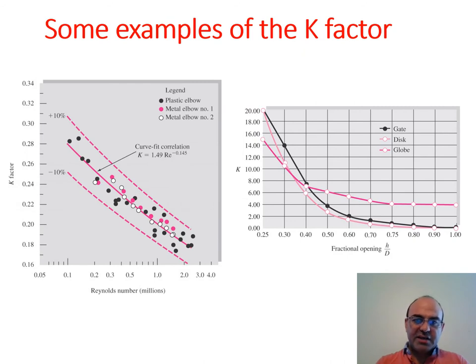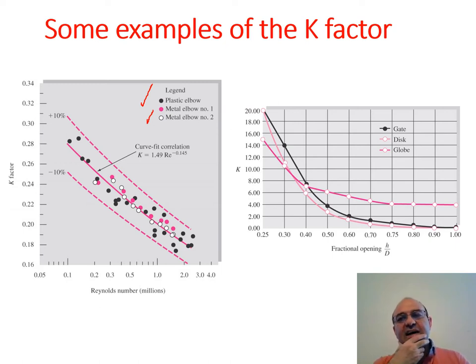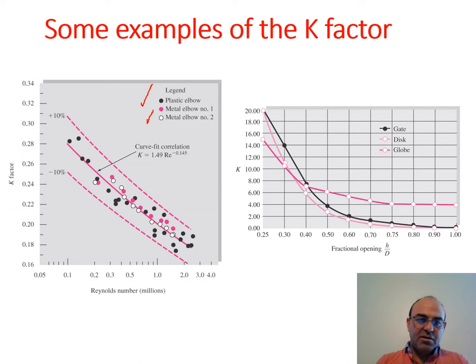Some examples of K factors: for plastic and metal elbows, K is given as a function of Reynolds number. K is defined as hm divided by v²/2g; as the velocity changes, that must be taken into consideration. As shown in the curve, K decreases with increasing Reynolds number — the x-axis is in millions on a log scale, the y-axis is regular scale.